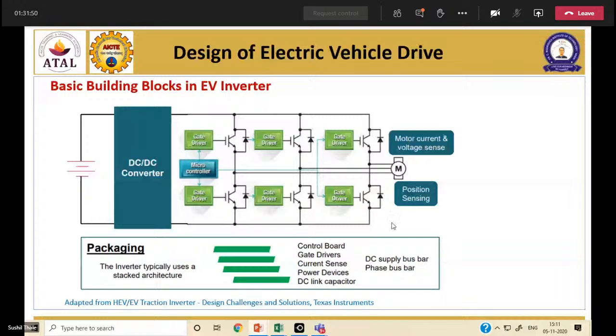So packaging is a separate entity in the inverter design, but otherwise achieving a very small footprint, including control boards, gate drivers, current sense, power devices, DC link capacitor, bus bars, protection devices, everything into a very small footprint, is the biggest challenge. If I think of a 150 kilowatt solar PV inverter, I can visualize a big, half-size cupboard as that size. But for the EV inverter, I want it to be just like double the size of my laptop, stacked together—that can be the size of the inverter I have to design. So the whole thing changes because it is all packed into a very small footprint, and other issues will pop up because of it.